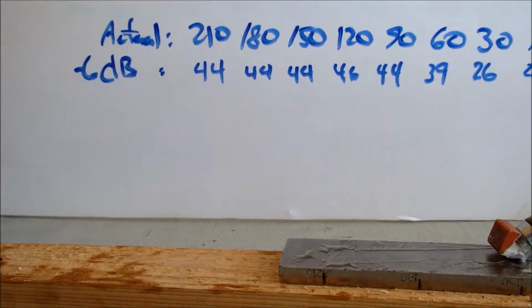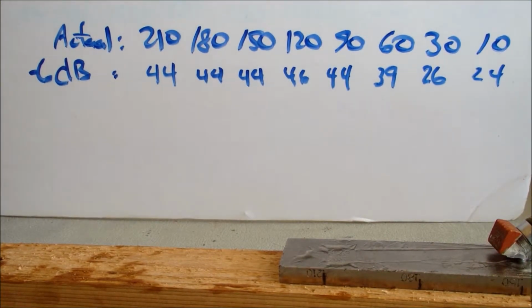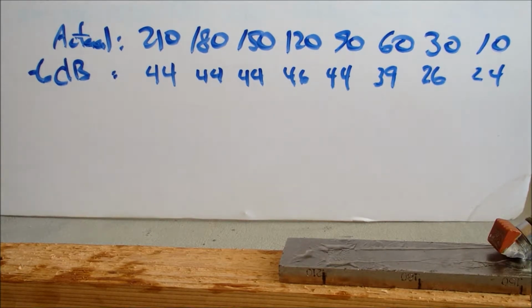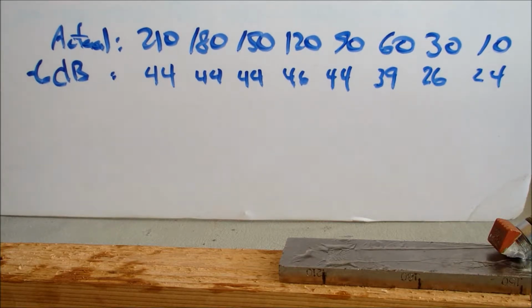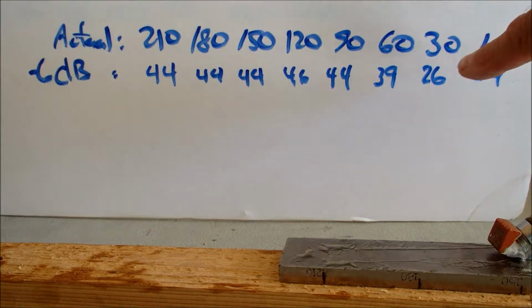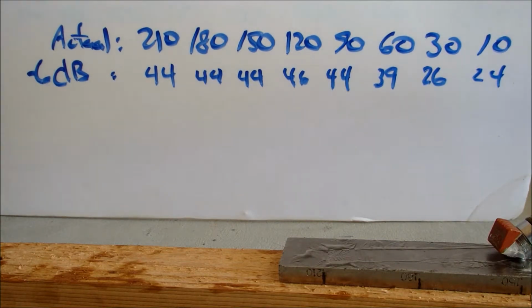So we end up with numbers that look like this. So I'm going to say that by coincidence on some of those lower numbers it's not too far off. It's only off by 4 thousandths on the 30, and it's only off by 14 thousandths on the 10. But after a certain point they all measure the same size. I think that has more to do with the size of the transducer. So the 6 dB drop technique does not work for flaw height sizing. All right, thanks.